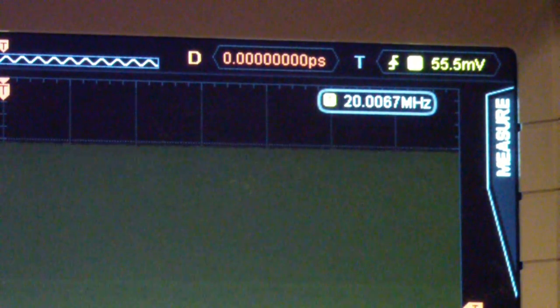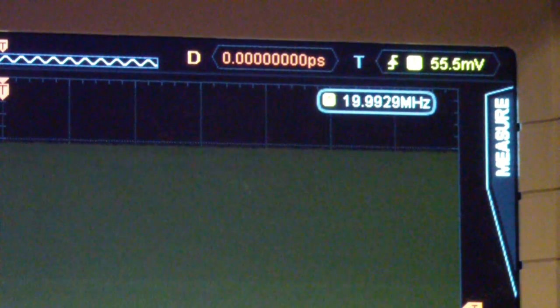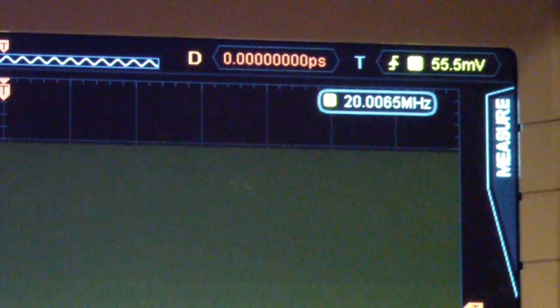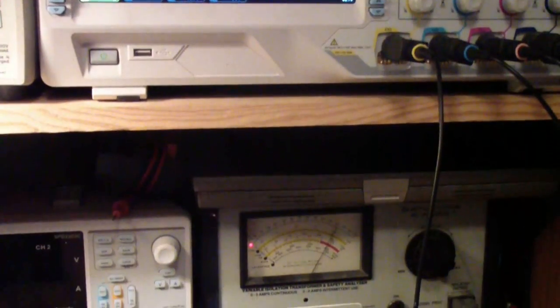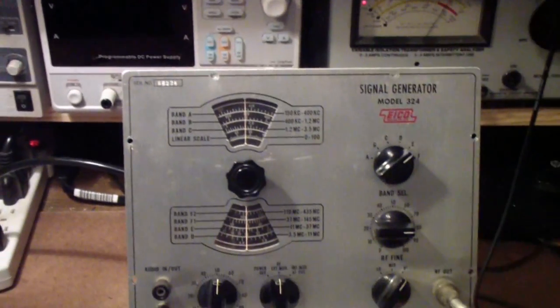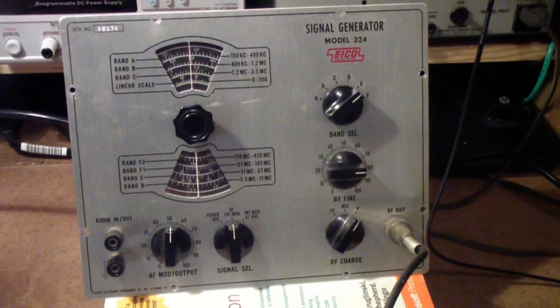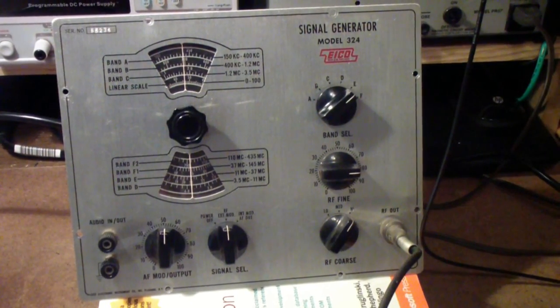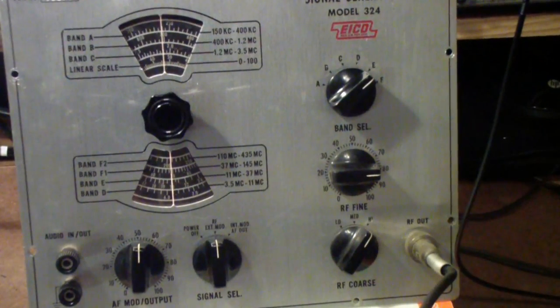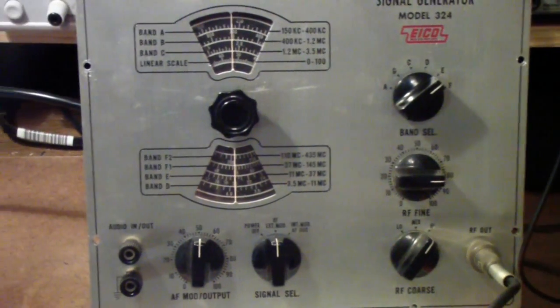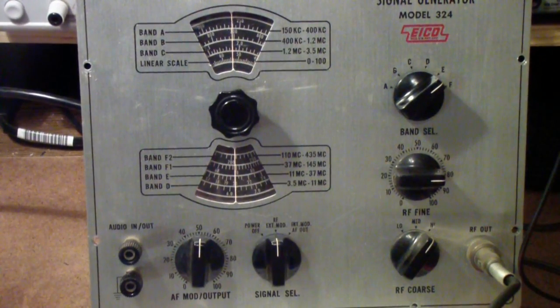So I have checked the calibration, the mid-band calibration of all of these bands, as well as the end-to-end from band A through band E. And I point out that band F is actually not really a band, it's really just a harmonic of band E. So if band E is calibrated, well, the harmonics on band F will also be correct.